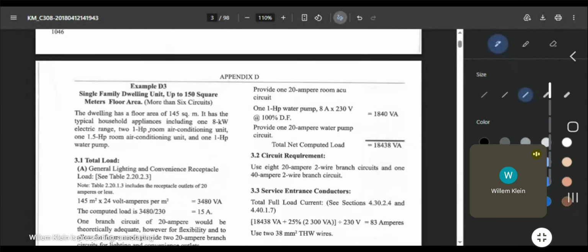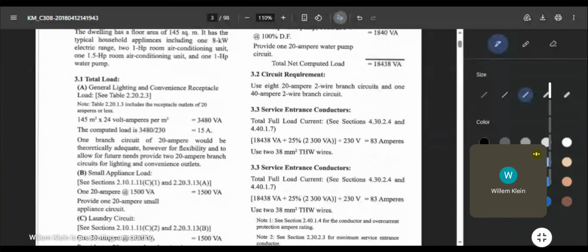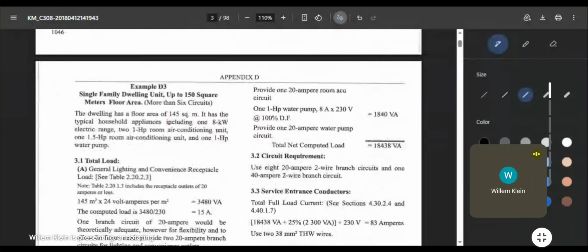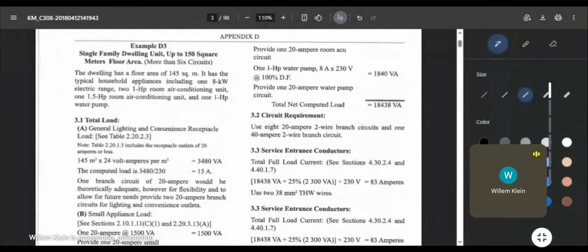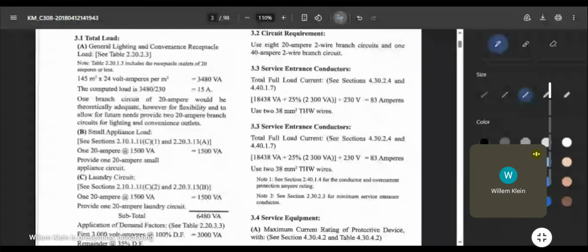Okay, but more than 6 circuits. Okay, so let's just see the difference with this one and the previous one. Aside from, of course, this will have more than 6 circuits. So for your general lighting and convenience, we will still use the area method, 24 volt amperes per square meter. Same lot area or floor area. So you have 145 square meters times 24, so you'll have 3480 VA.